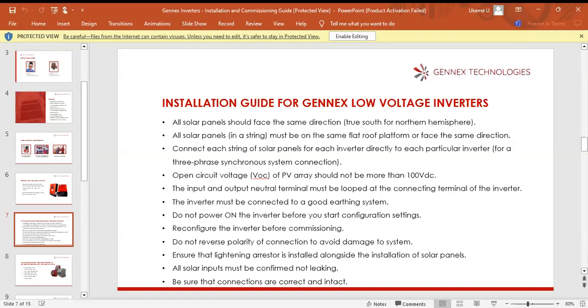The open circuit voltage VOC of the PV array should not be more than 100 volts. It's advice, so that you won't be thinking, when something happens, that it's because you are operating at the maximum. So it's better to operate below that maximum. In essence, you are connecting 2 panels together. The input and output neutral terminals must be looped at the connecting terminal of the inverter. This is also important.